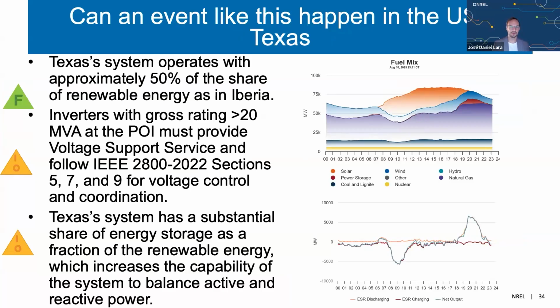In the Texas code, inverters with gross rating of more than 20 MVA have to provide voltage support according to IEEE 2800. Texas has a substantial share of energy storage, and every single inverter-based unit, whether solar, wind, or storage, has to provide this voltage control.